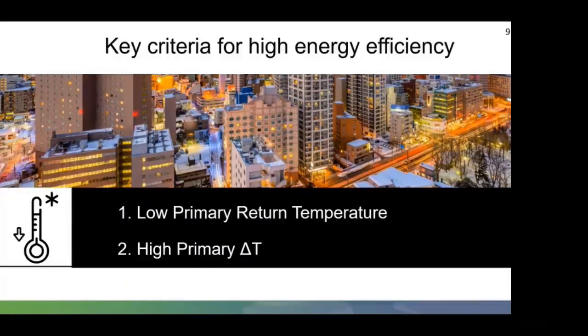So key criteria for high energy efficiency. By looking at the world's biggest heat networks, we can learn some very valuable lessons. Small changes can increase the efficiency and maximize the use of energy. The key to high energy efficient heating systems is the lower primary return temperature and a high primary delta T. The more efficient the system itself becomes. So what you're looking at is low primary return temperature, high delta T. So you're extracting as much energy as possible out of the flow that goes into that building.